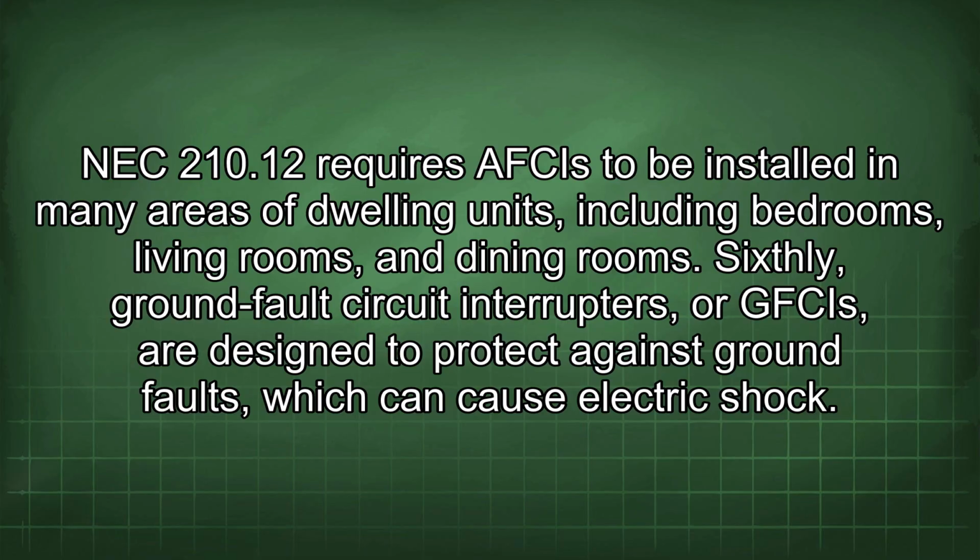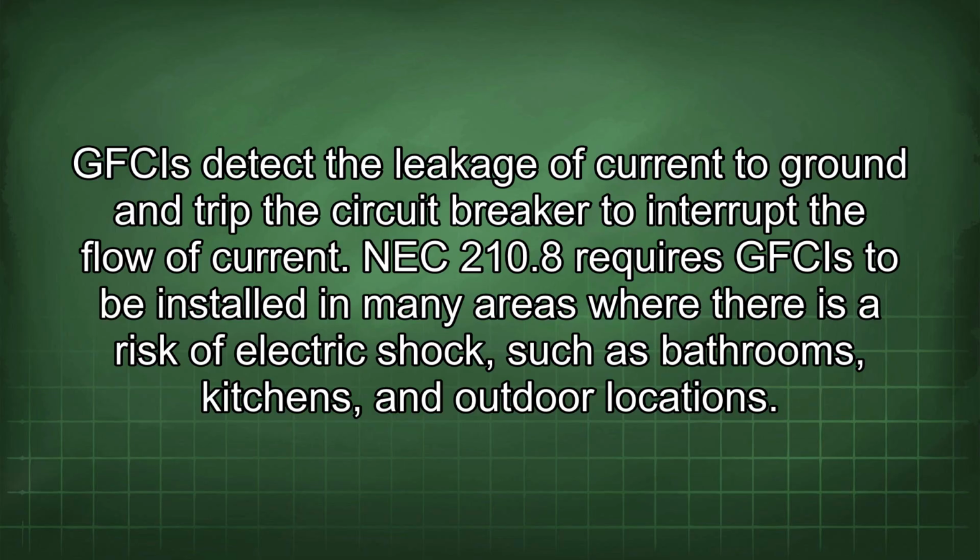Sixthly, ground fault circuit interrupters, or GFCIs, are designed to protect against ground faults, which can cause electric shock. GFCIs detect the leakage of current to ground and trip the circuit breaker to interrupt the flow of current. NEC 210.8 requires GFCIs to be installed in many areas where there is a risk of electric shock, such as bathrooms, kitchens, and outdoor locations.